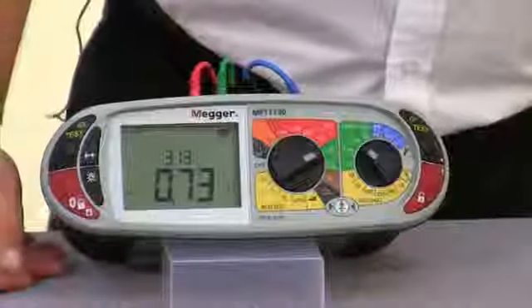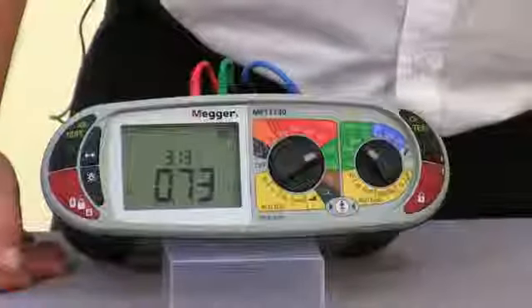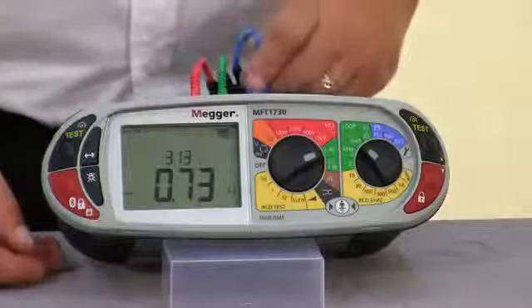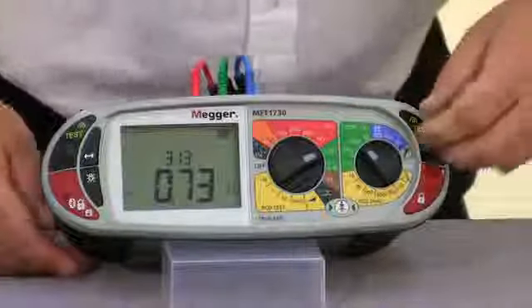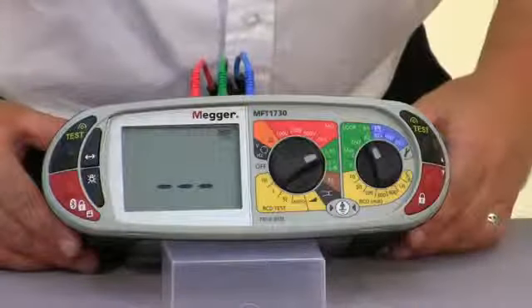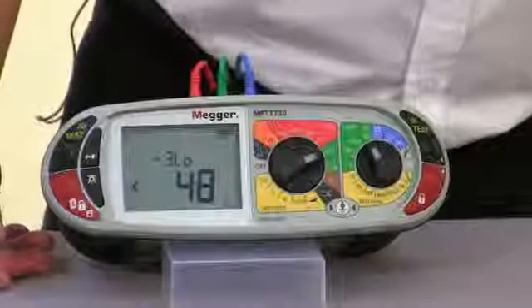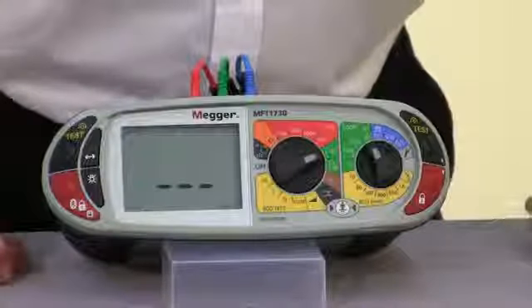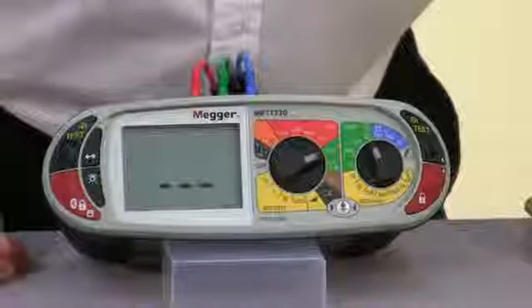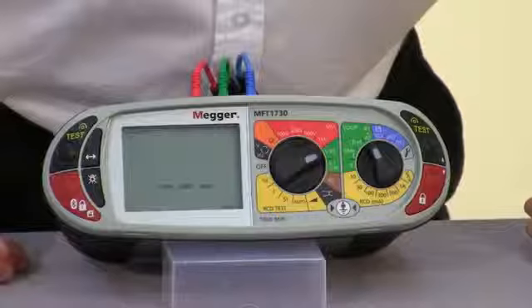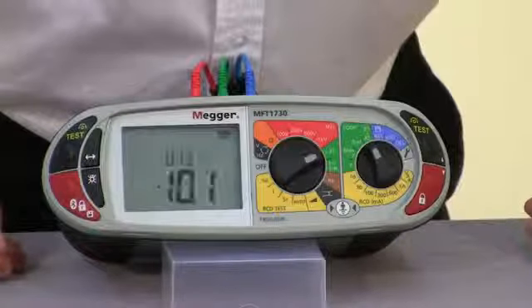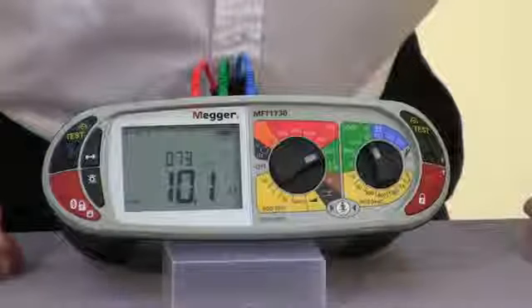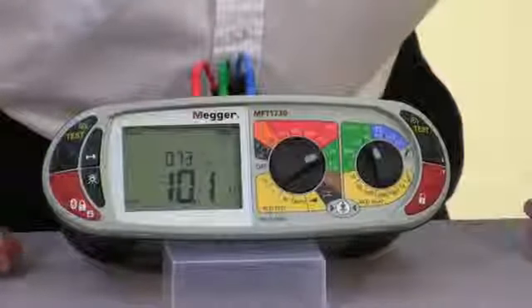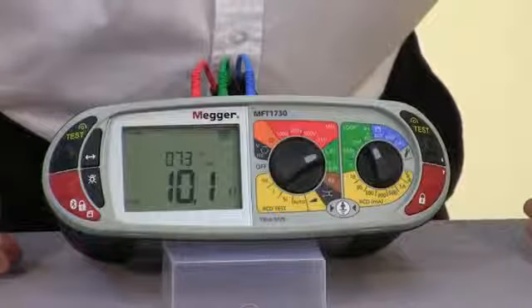So now, without turning the unit off, we will connect for a 3-wire no trip test, and we select our R1, R2. Again, plugging the unit in. So this is our ZS at our socket. The ZREF, which was our ZE value, which we've now saved on the unit, will be deducted away from the second reading. So as you can see, it's indicating the Z reference at 0.73, and it's given us a value of 10.1.